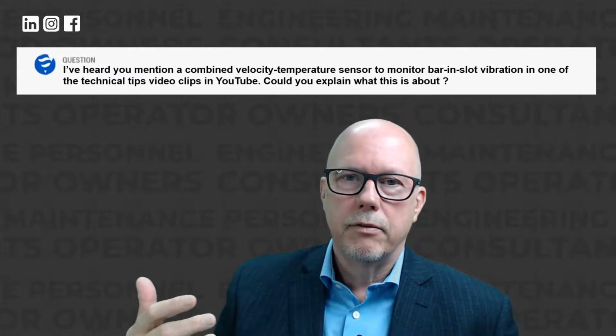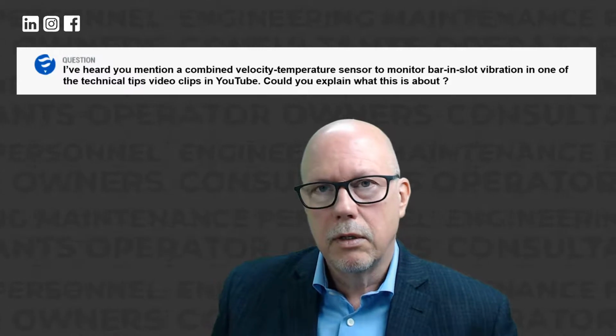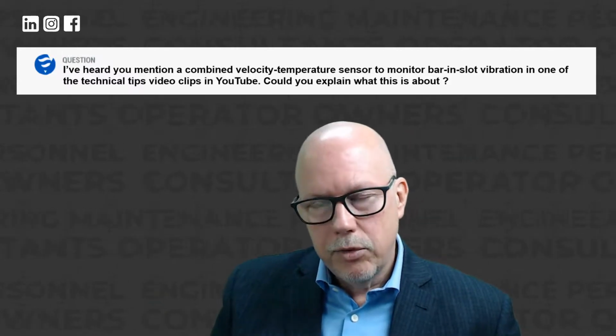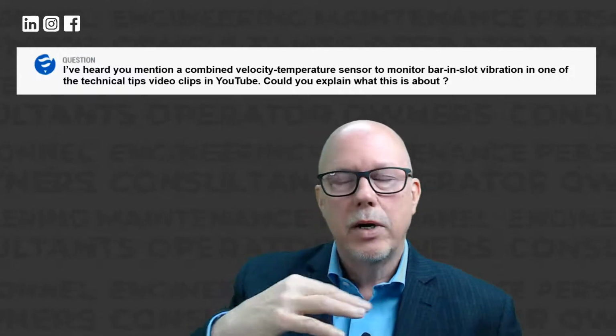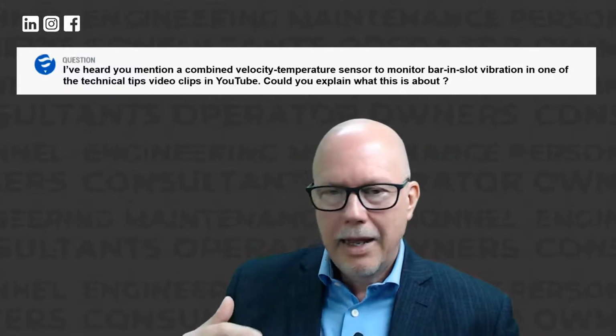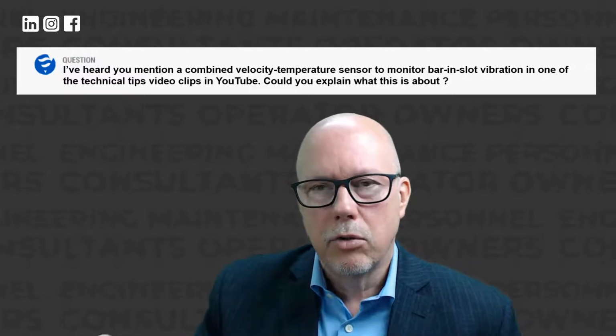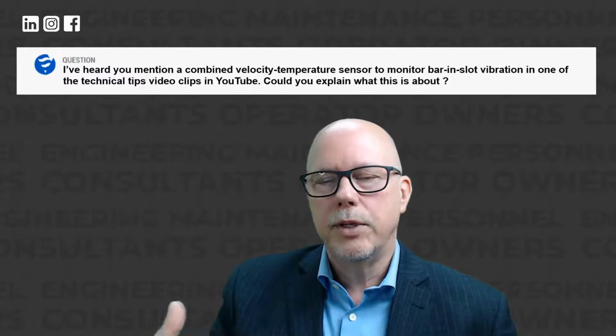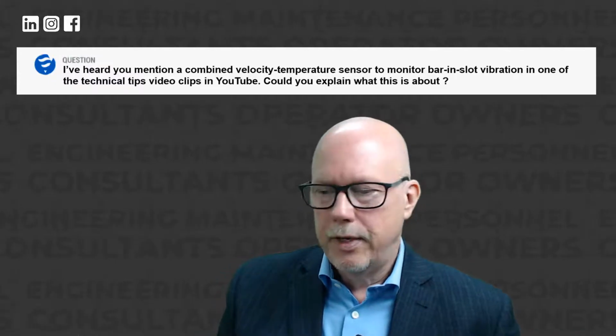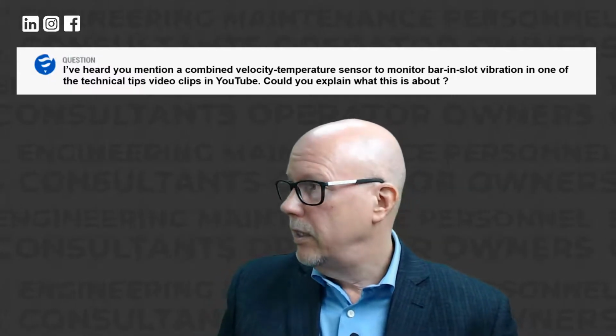So you can corroborate or compare vibration levels to temperature levels. We feel this is a very elegant, non-intrusive approach to give you the best coverage possible for the entire windings on the stator core, and a first level assessment as to whether there are issues or serious problems that need investment to prevent a major failure. It's very cost effective—I'd say a breakthrough. We're very happy about it and looking forward to seeing it deployed everywhere, with lots of interesting results.